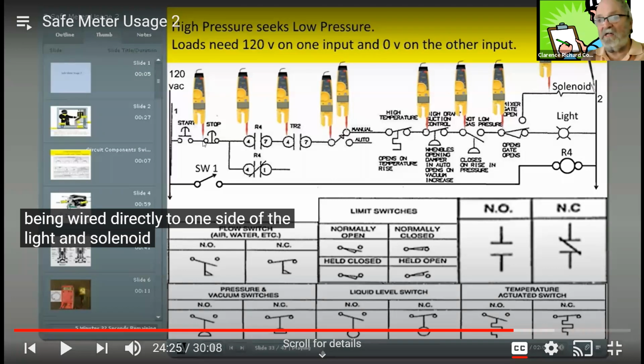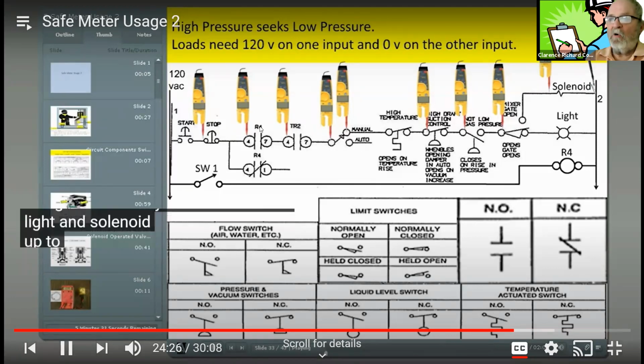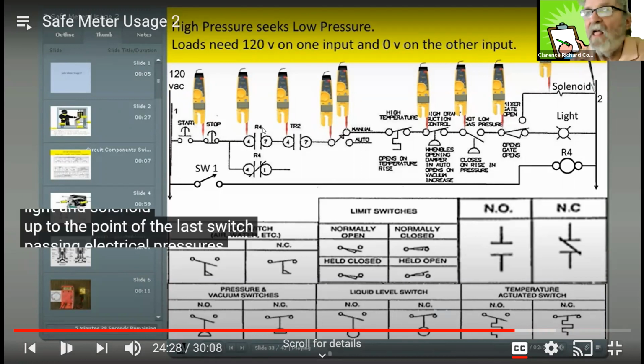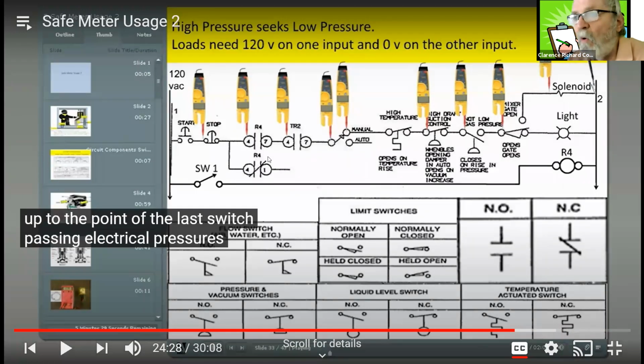This is a normally closed set of contacts on the stop switch, so all we've got to do is not touch it. Don't push it. And then from that point, we get to an R4 set of contacts. We look for a coil passing electrical pressure, a coil that says R4. Oh my God, here's a coil that says R4.